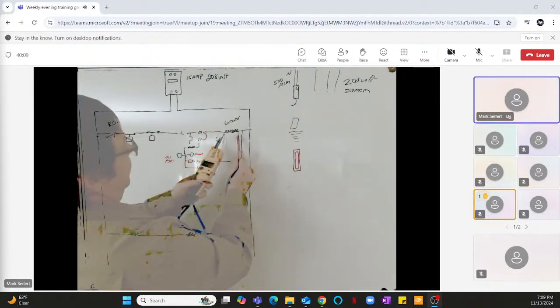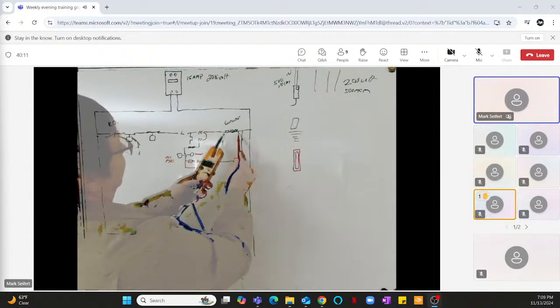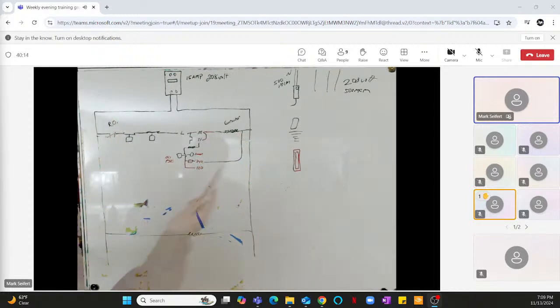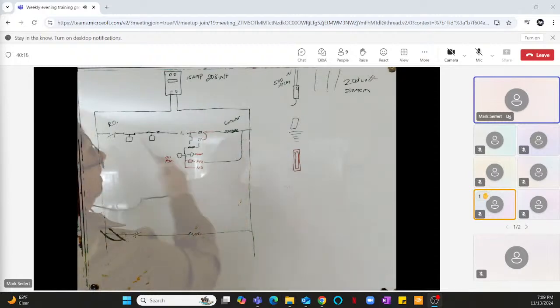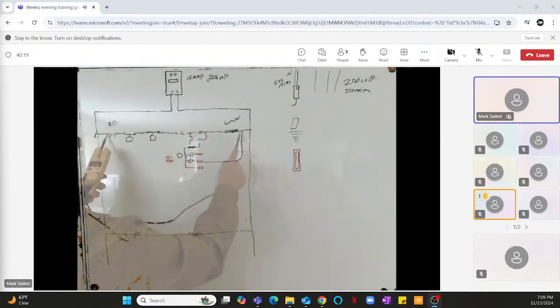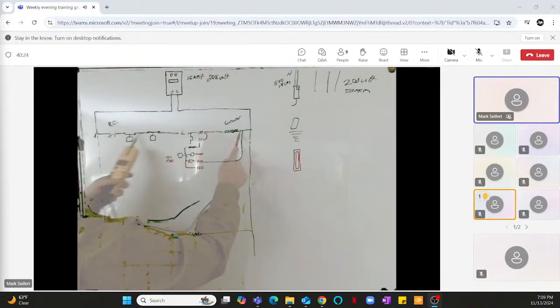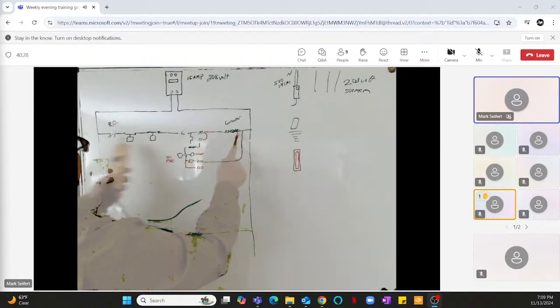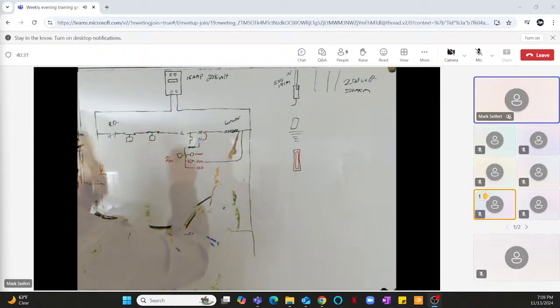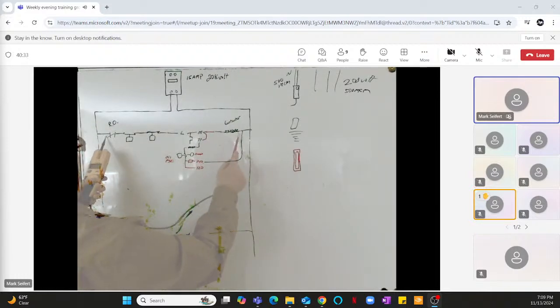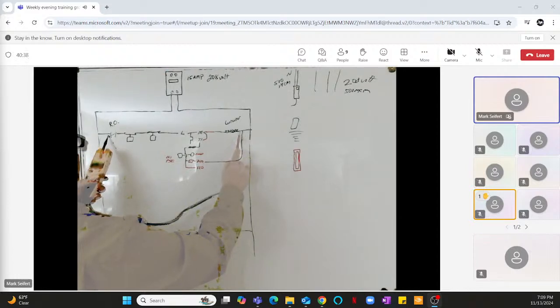If you got no power here either across that, now you've got something weird going on, and you got to work your way back in. You'll check here to here. Do I have 208 here? Yes. All right. So there's something going on in here somewhere, but you don't know where. Most of the time it's going to be a wire nut popped off or whatever. But then you would check like this. You would check over here, and you would go like this. Boom, boom, boom, boom, boom, boom. You'd find it in there.